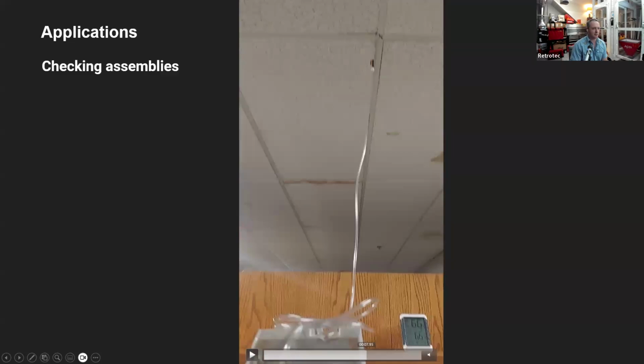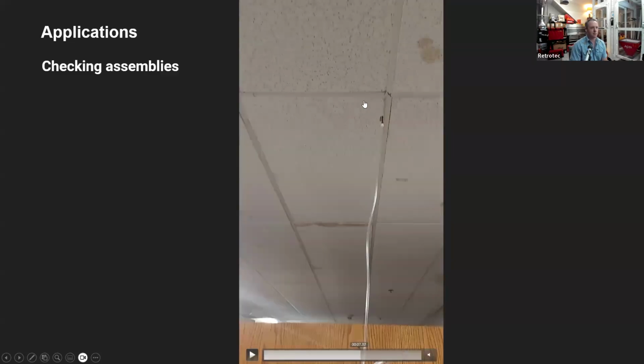What you don't see is above these ceiling tiles is the air handler duct system, and above that is just foil-backed insulation tacked up to the trusses. Whoever installed that was thinking it would act as an air barrier, but it was riddled with holes, not deliberately sealed at the seams, and some areas were falling down.